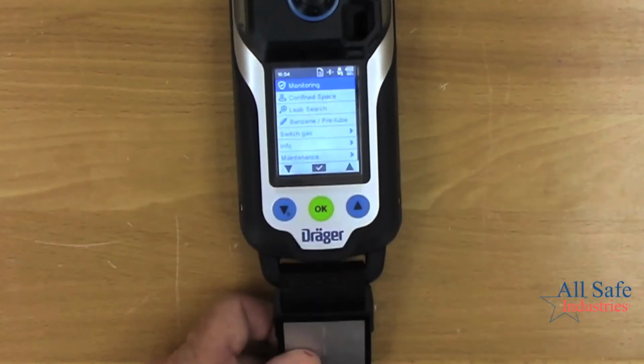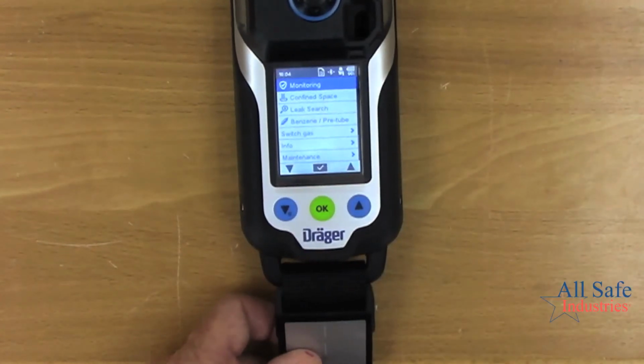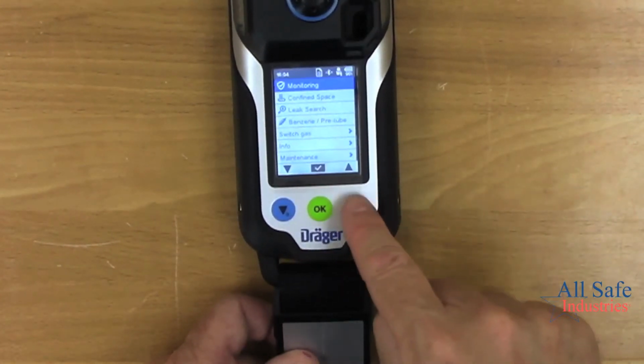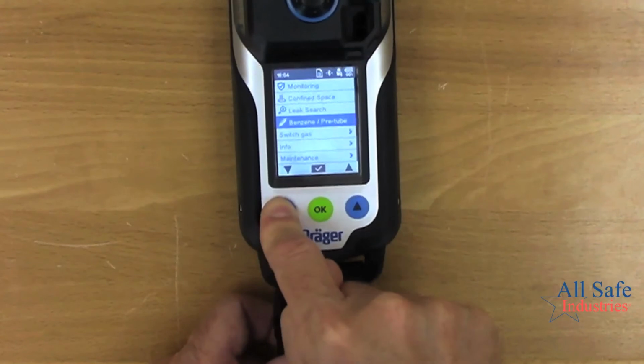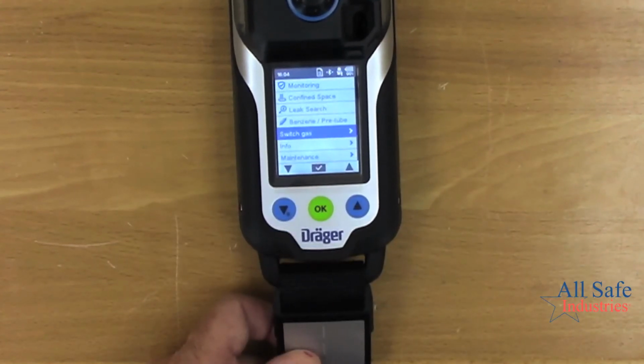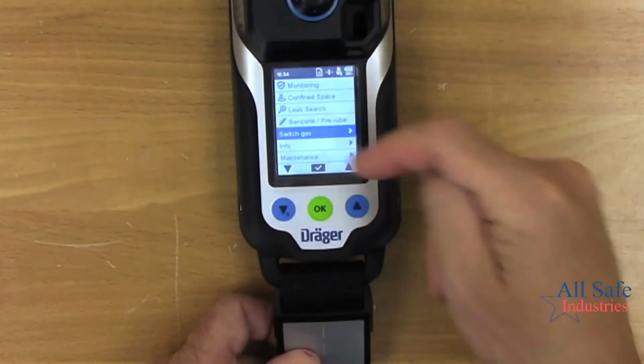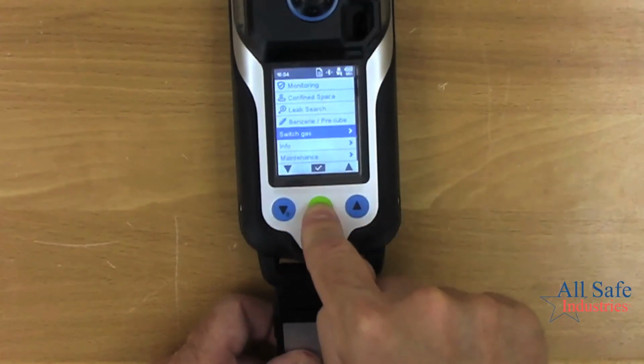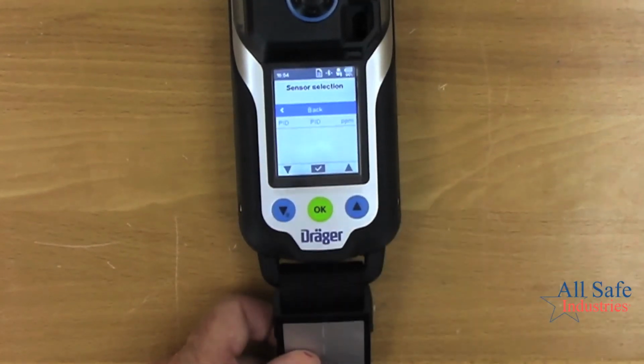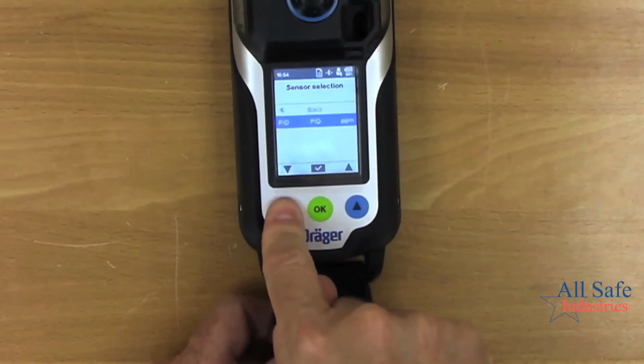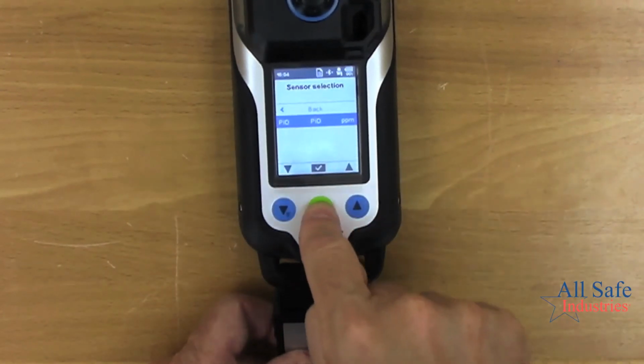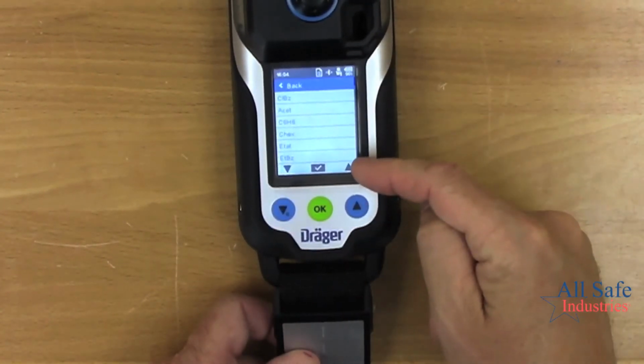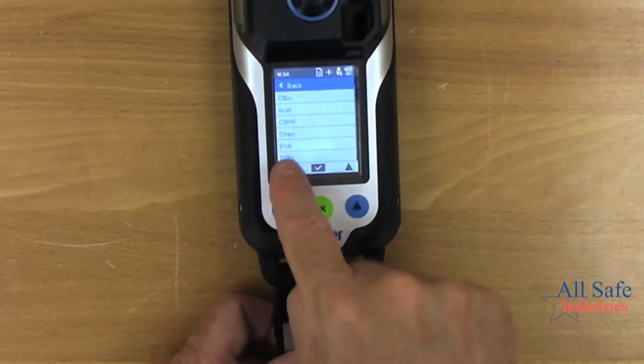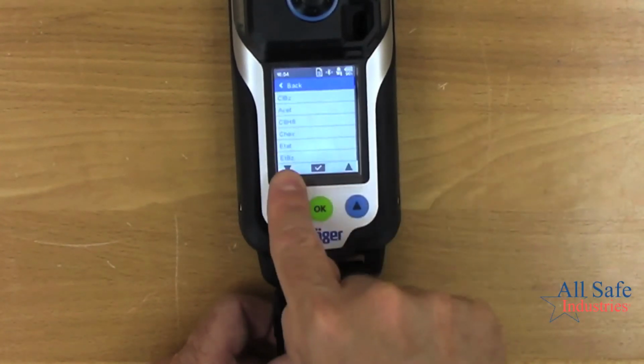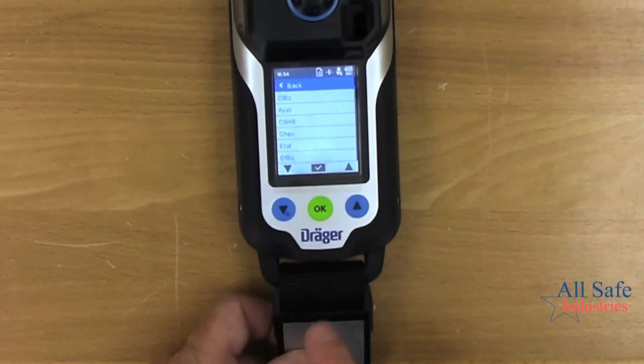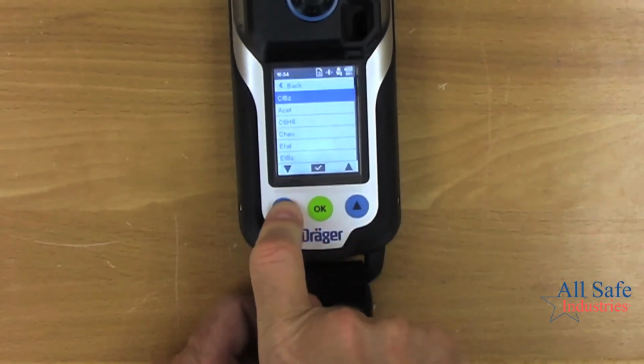I'm going to X out of that, and now I'm back to my main menu. You also have the ability to switch the gases on the PID channel. So if you're familiar with correction factors, the X-am 8000 has a built-in correction factor menu. If I say OK to that, it's asking me which sensor I want to change, and it would be my PID sensor. Then you have, I don't know how many it is, but several choices with some abbreviations. So you'll have to know those abbreviations, but I'm sure you know these.